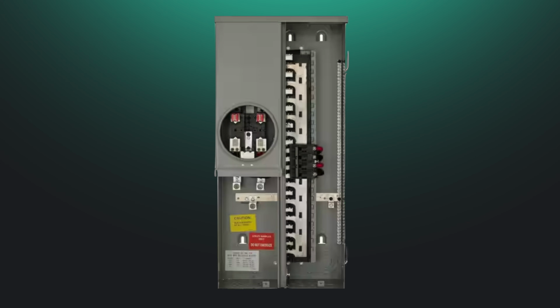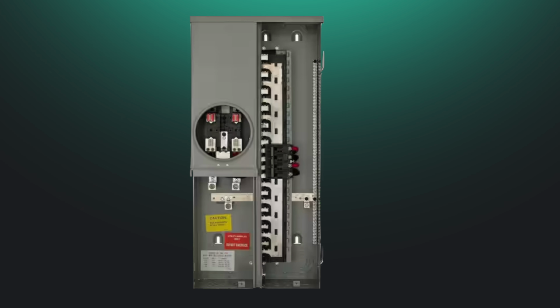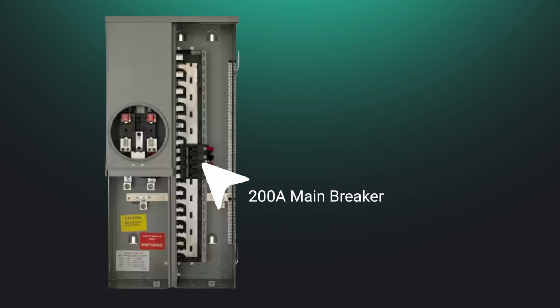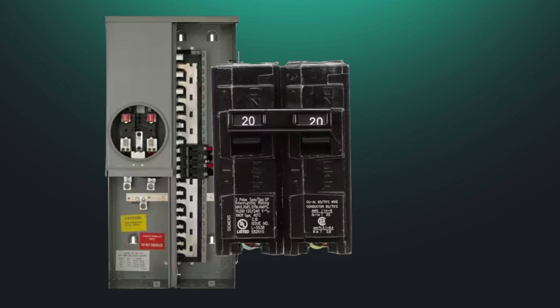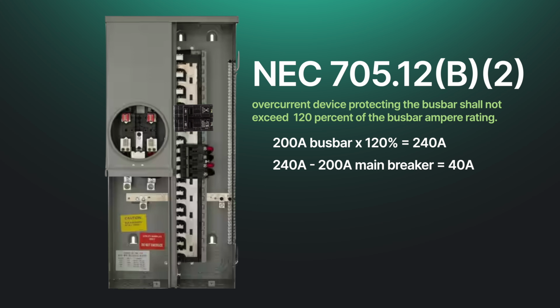Here's a simple example of how this 120% rule works out. Imagine you have a standard 200 amp electrical panel with a 200 amp main breaker and a 200 amp busbar. The busbar is the metal backbone that distributes electricity throughout the panel. Every breaker in the panel connects directly to this busbar. Under the 120% rule, we take the busbar rating and multiply it by 120%. So a 200 amp busbar multiplied by 120% equals 240 amps. From that number, we subtract the main breaker rating. So 240 amps minus the 200 amp main breaker equals 40 amps. What that means is that under traditional installation methods, a standard 200 amp panel can only accommodate up to 40 amps of solar or battery backfeed without additional modifications.